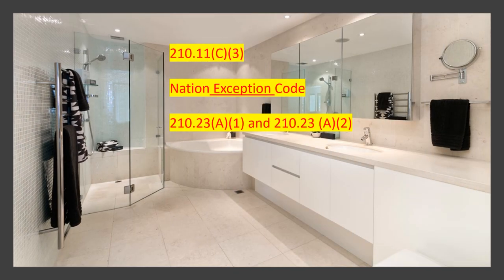All right, when we flip over one page, I first want to read 210.23(A) and then we'll read sections one and two. Section A says: a 15 or 20-amp branch circuit shall be permitted to supply lighting units or other utilization equipment as long as it complies with A1 and A2. I want to note that today we're specifically talking about a bathroom, but this applies to any circuit in general — it's allowed to run lighting as long as it hits these two points.